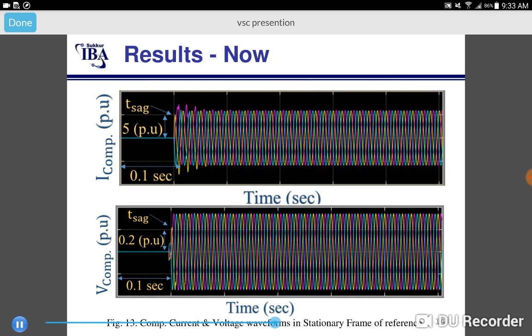The grid voltage, which is not shown here, at the utility side is 1 volt initially, but as soon as the sag occurs, that is at T sag here, which is equal to 0.096 second, the utility voltage is reduced to 0.7 pu. So the compensator detects the sag and it starts at T equal to T sag. After a delay of 0.004 seconds, this delay occurs due to the time required for the detection of fault and activation of bypass switches. Since the voltage at utility side has reduced to 0.7, the compensator injects V compensate voltage of 0.3 pu as shown here.